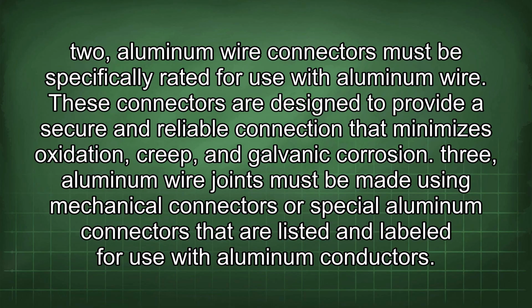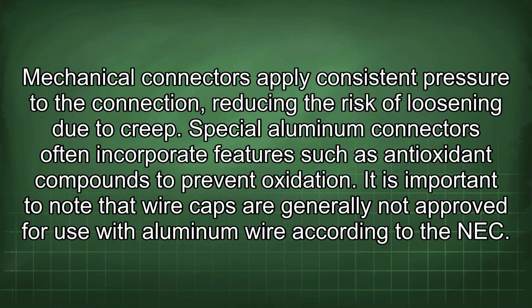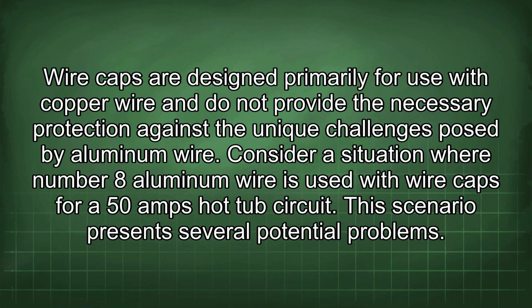3. Aluminum wire joints must be made using mechanical connectors or special aluminum connectors that are listed and labeled for use with aluminum conductors. Mechanical connectors apply consistent pressure to the connection, reducing the risk of loosening due to creep. Special aluminum connectors often incorporate features such as antioxidant compounds to prevent oxidation. It is important to note that wire caps are generally not approved for use with aluminum wire according to the NEC. Wire caps are designed primarily for use with copper wire and do not provide the necessary protection against the unique challenges posed by aluminum wire.